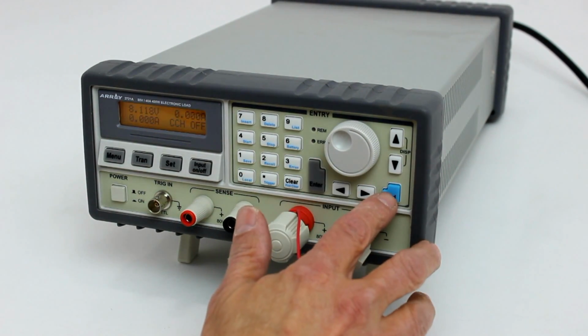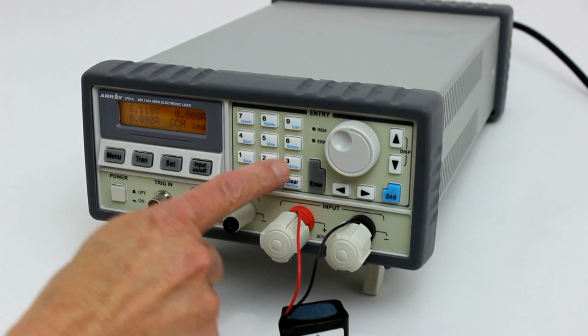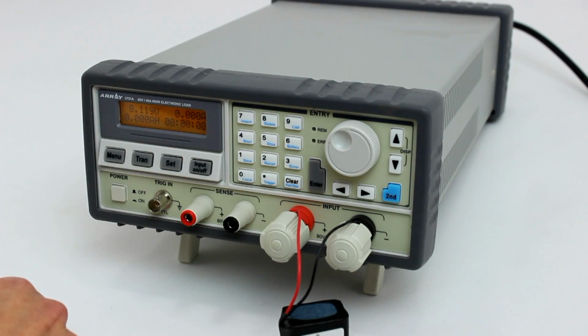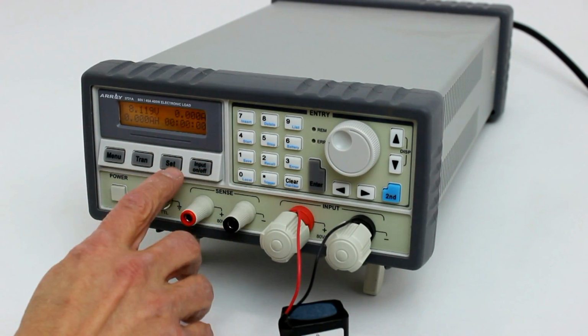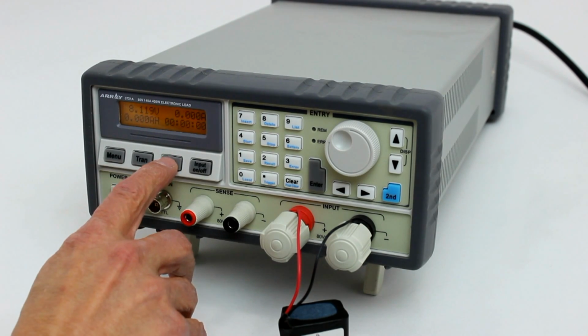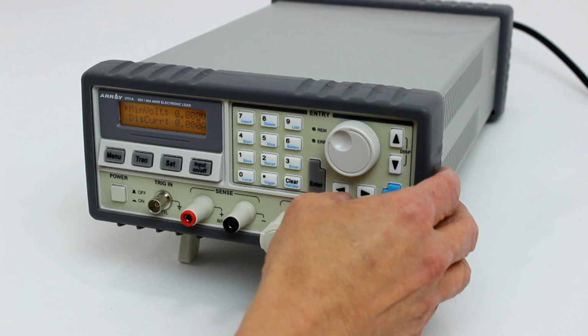Step 1. Power on the electronic load and press the input on-off button to disable the load, and then connect the battery pack while observing polarity. Step 2. Press and release the second button before pressing the sixth or battery button to enter battery discharge mode.